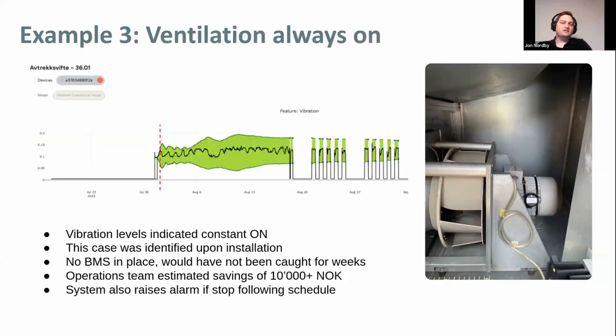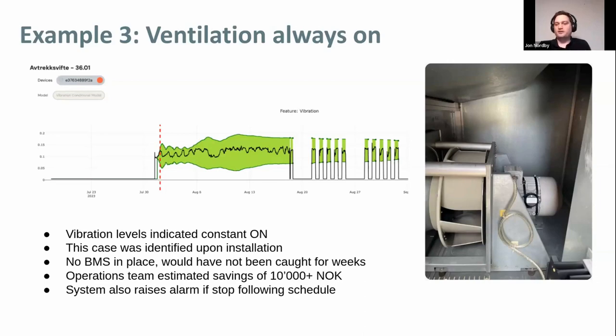We also learned that, somewhat surprisingly, it's quite common in buildings that equipment is sometimes on when it should be off or off when it should be on. There are a wide range of sources, including configuration problems, software, and communication protocol issues. Here's an example of a system that was running day and night continuously, regardless of if anyone was there, and had been going on for several weeks unnoticed. This was spotted during our installation, but the system also automatically flags this if it would start to appear after a normal scheduled pattern, as you can see on the end here.